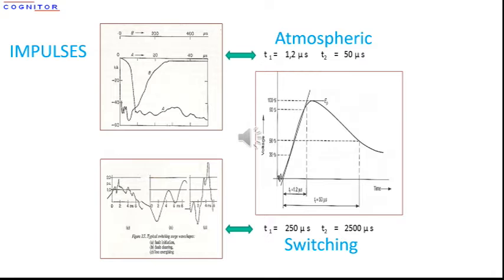These waves are produced by the so-called impulse generators, which are banks of capacitors having some resistors in series, and by adjusting the values of these capacitors and resistors, we can produce an impulse wave which is, as well as possible, representative of what happens in the network.